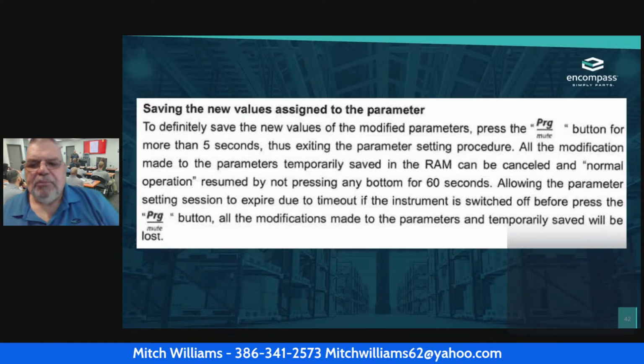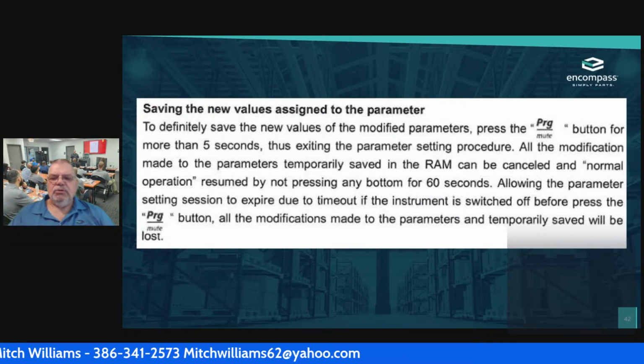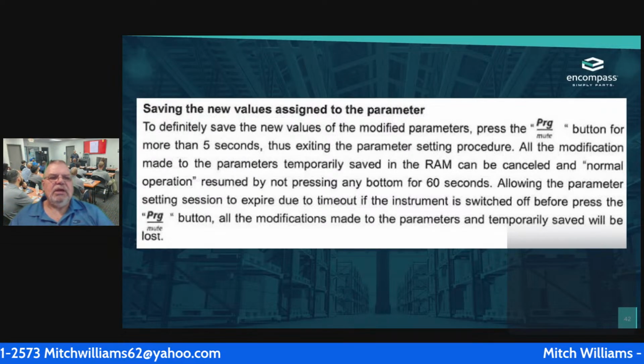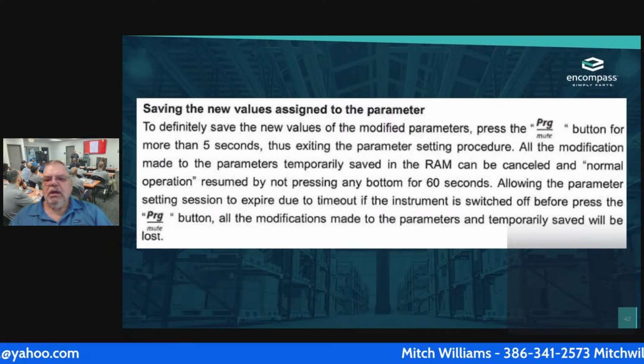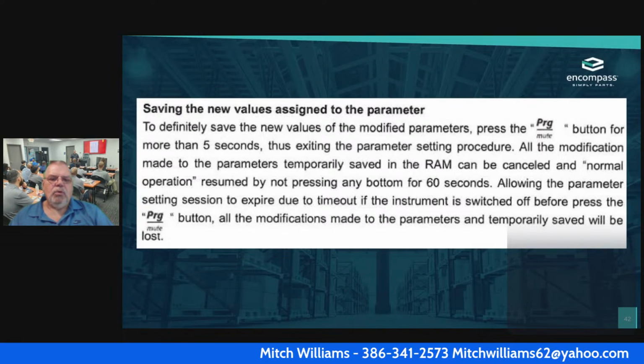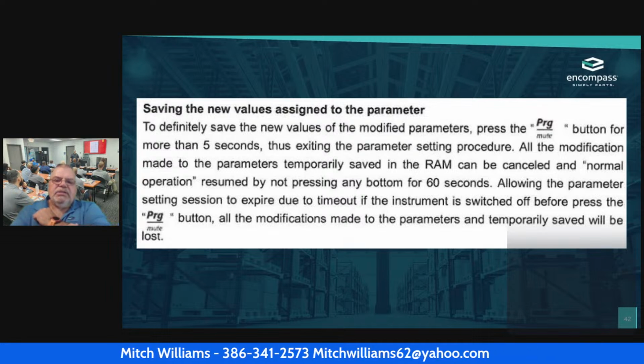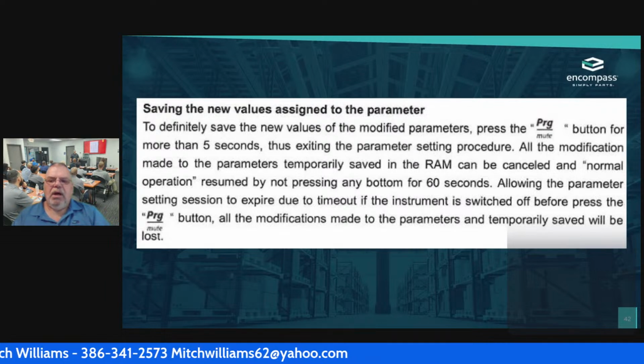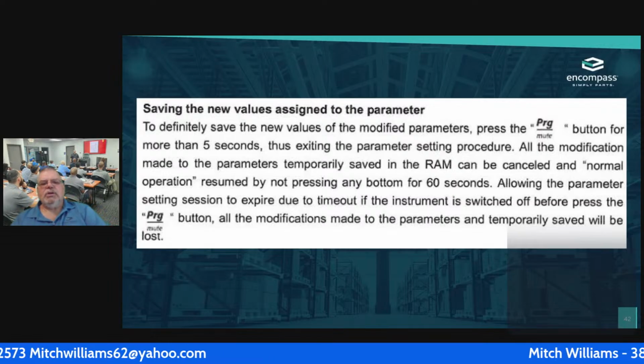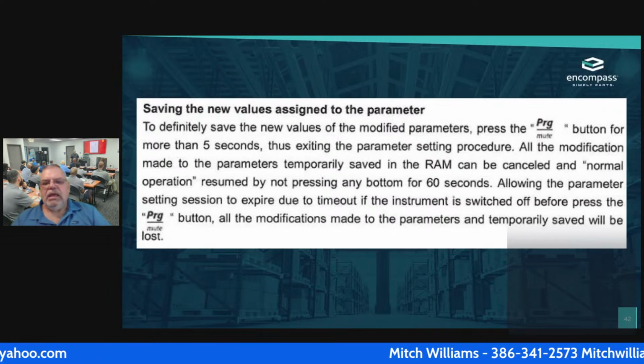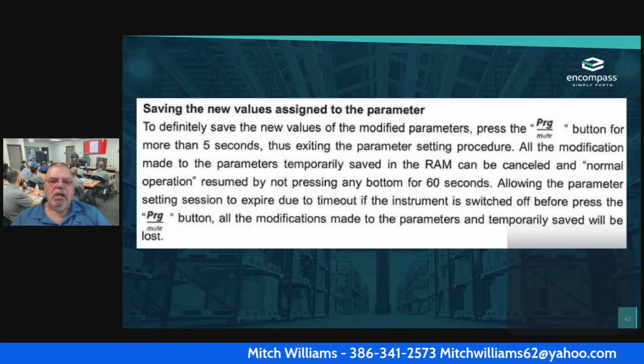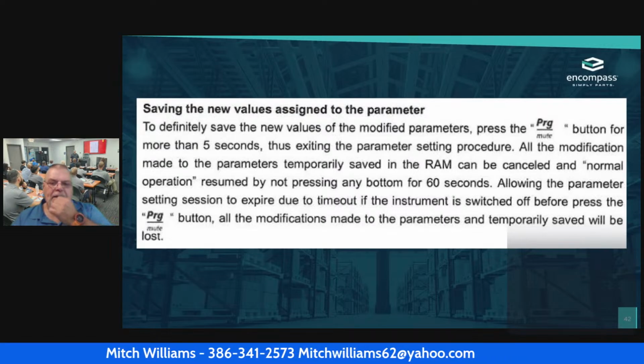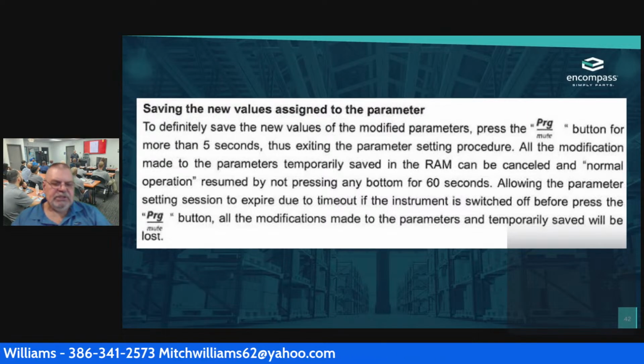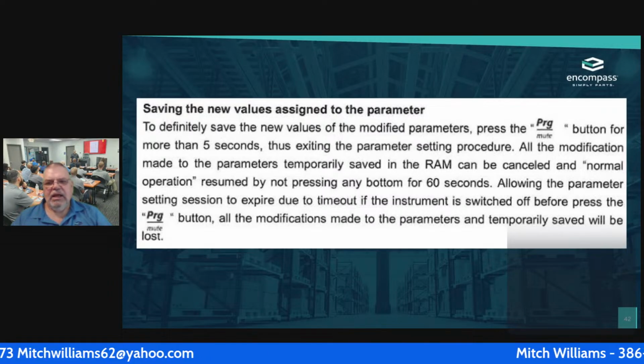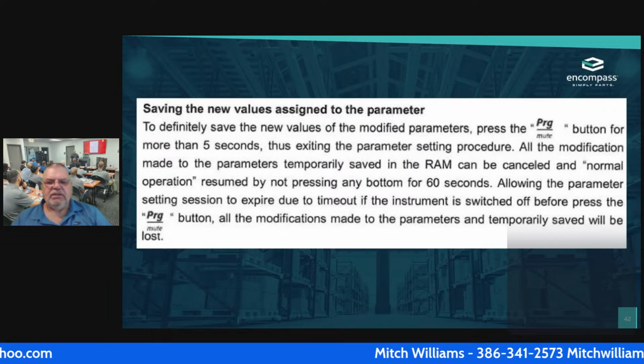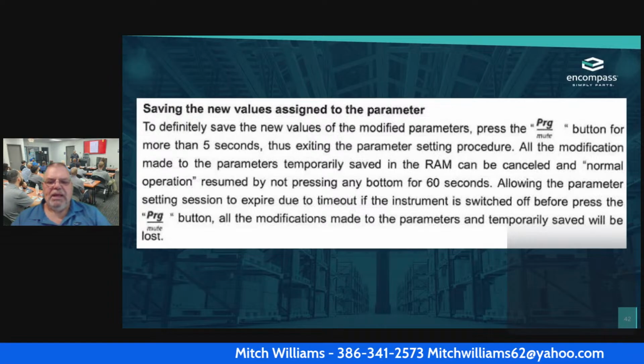Okay. So if I'm definitely going to save these, I'm going to press the program button for more than 5 seconds, thus exiting the parameter setting. All modifications to the parameters are temporarily saved in the RAM and can be canceled, and normal operation resumed, by not pressing any button for 60 seconds. So if I don't want to save it, I just don't do anything, and after 60 seconds it will revert back to the other setting.